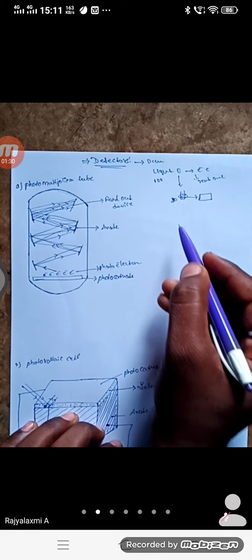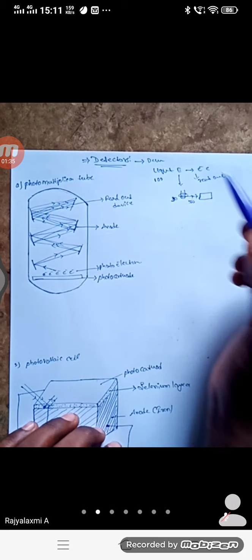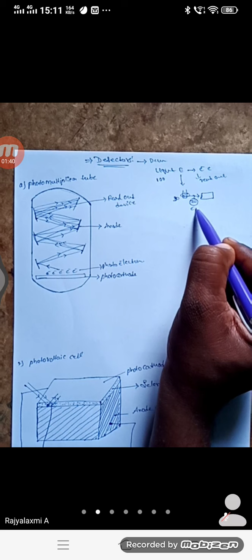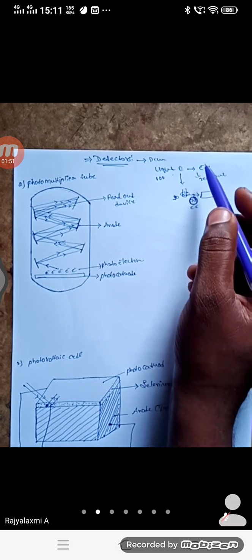For example, the light energy is 100. Of the 100, the sample cell absorbs 30, and the remaining 70 is the emitted energy. That emitted energy is read out by the detectors. So the 70 becomes the electrical signal. Before the sample cell it is light energy, after the sample it is electrical energy, and this electrical energy is read out by the detectors. That is the importance of the detectors.